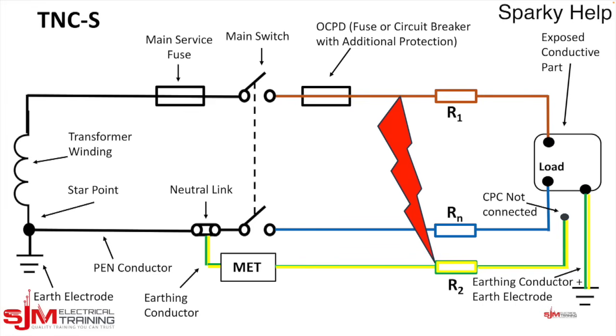But what would happen if you got a fault halfway along that cable? Bear in mind you've disconnected the earth. Well, we have got up here an overcurrent protective device, and I've said it's with additional protection. So additional protection is a 30 milliamp RCD, and it's connected at that point. And we've got a fault, so someone's maybe dug your cable up and they've put a spade through it, and as they cut through the earth and hit the line conductor, we create a fault. Obviously, it's something that's going to go bang, but current will flow in this direction and back through the armouring, of which your overcurrent protective device will either go, if that's what you've got, or your RCD will pick this up and disconnect it.